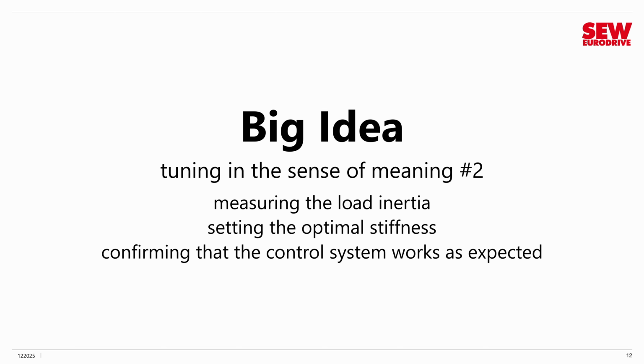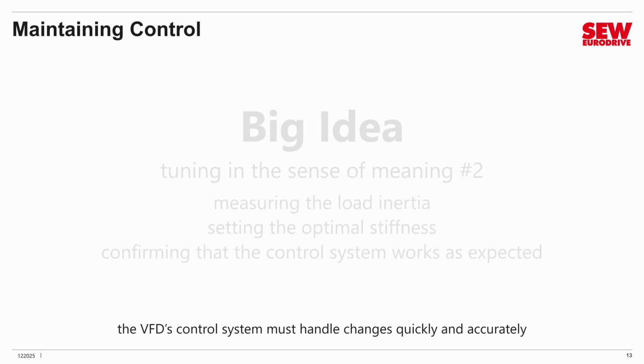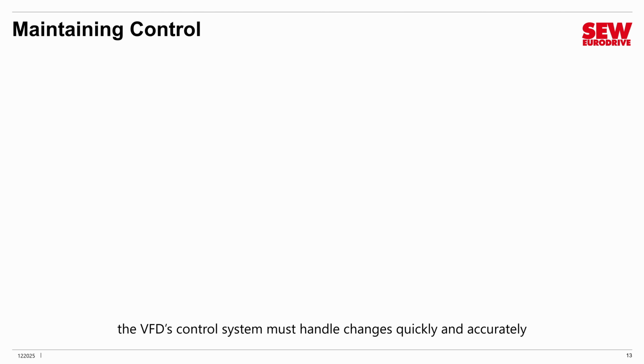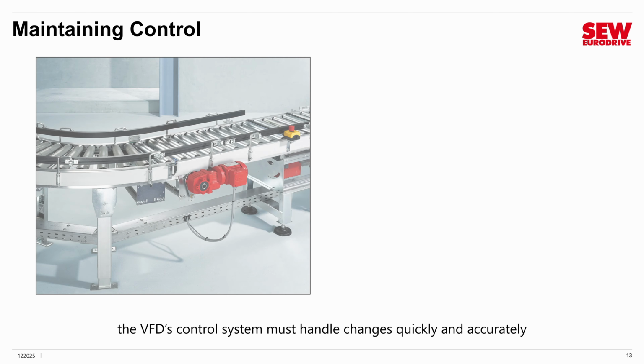And then finally, when you do this, of course, you've got to confirm that the control system really works as expected. This is one of those art forms of commissioning, and some people are better at it than others, but it's important, especially with challenging applications. Let me talk about something closely related to this kind of tuning, and that is maintaining control of the load. The VFD's control system needs to handle changes quickly and accurately when it's controlling the application and the load that it's attached to. Let me give you an illustration of this. We have a simple conveyor here. The conveyor at this point is empty.